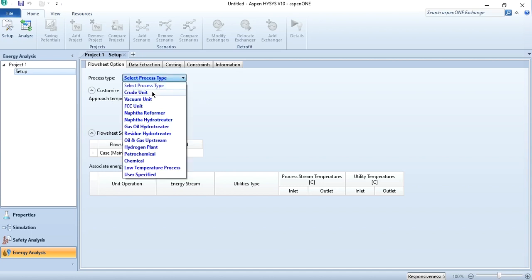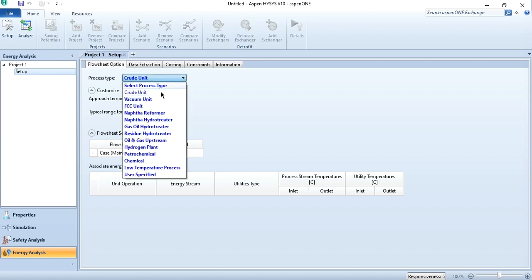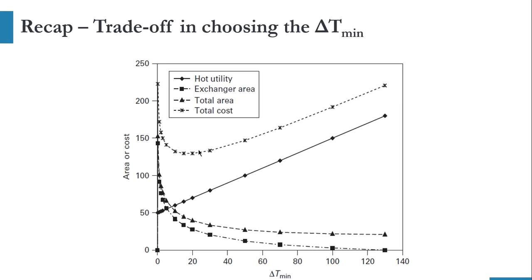For example, if it's a crude unit, you can see the typical range for the crude unit — the value of approach temperature is 10 to 25 degrees centigrade. Similarly, if you want to know for the vacuum unit, this value may vary to 20 to 30. So if you remember our previous exercise in which we had discussed a graph, we had selected the range of 10 to 20 degrees centigrade, but that is not always true. It varies from process to process. In the vacuum unit, this value goes from 20 to 30 degrees centigrade, while in the crude unit, that value was between 10 to 25 degrees centigrade.